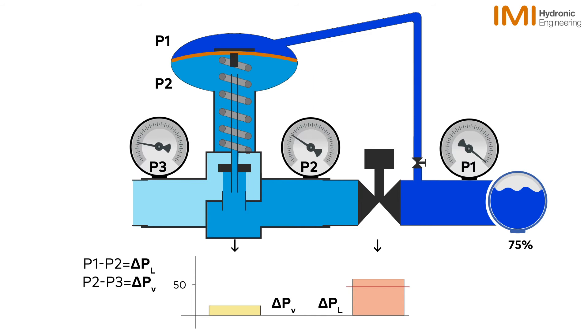The DPCV will act upon this change by closing down, thus increasing delta PV and decreasing delta PL back to set point.